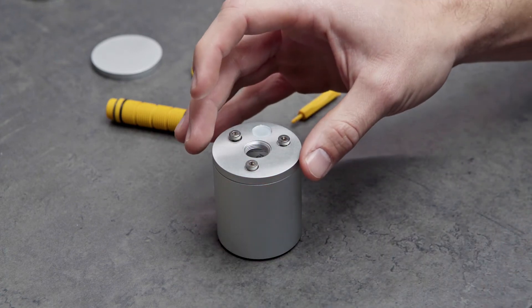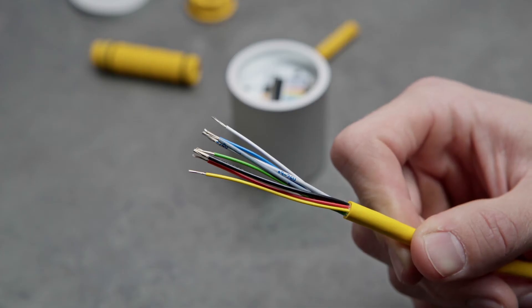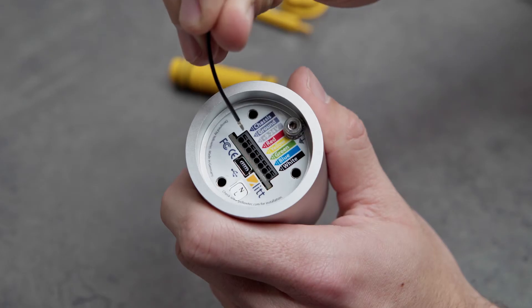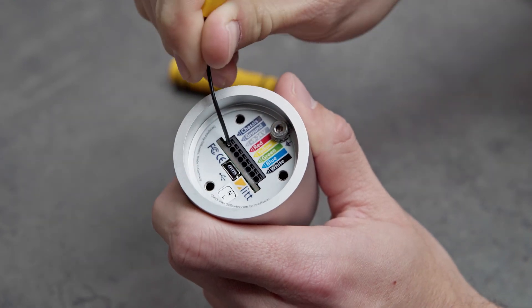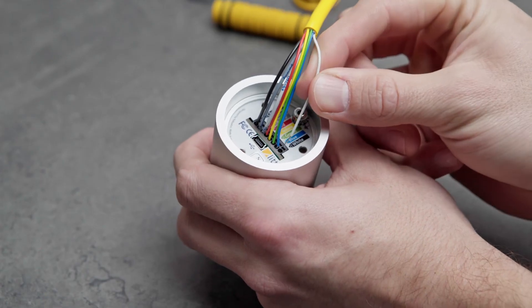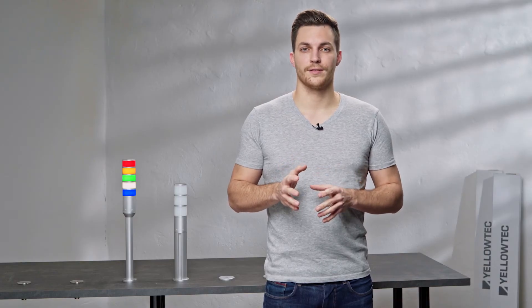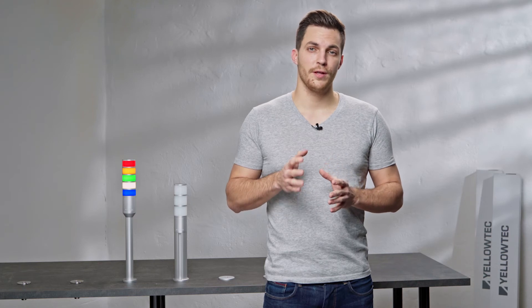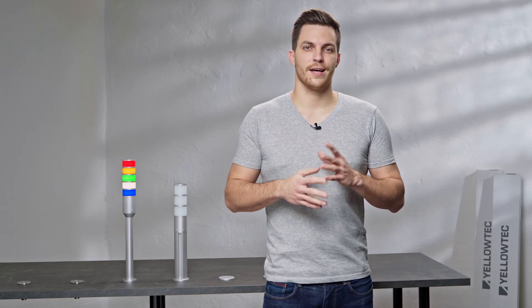The connection panel of the base controller consists of an 8-pin terminal block for cable connection. If you are using a LID system cable, you can easily attach the wires of your custom hybrid cable to the matching colors on the port panel. LID needs a permanent voltage between 9 and 24 volts. 2.4 to 24 volts are needed to control the segments. You can set up the threshold value within the Lighthouse software.